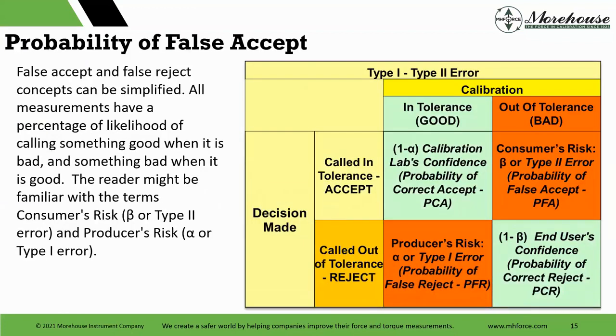But when we look at that, that's simplified, but it's very important to think about this. What is a false accept and a false reject? And what's the consequence of the false accept? If we don't account for measurement uncertainty properly, or if we don't understand how much risk we, as the end user, not as the calibration lab, as an end user, are subjecting ourselves to, that's a problem.